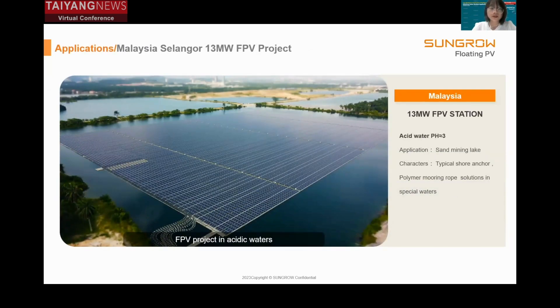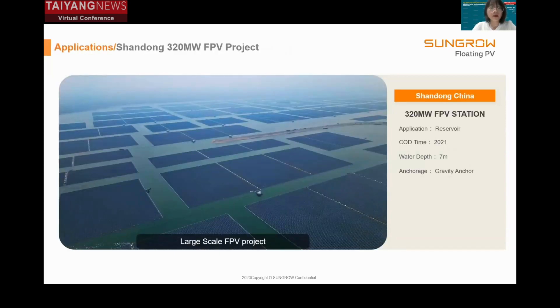This slide shows an FPV project under the competitive large-scale solar program in Malaysia. The water in the reservoir is acidic, with a pH of around 3. For this project, we applied a specialized design to avoid corrosion issues by using plastic solar module brackets and polymer mooring rope.